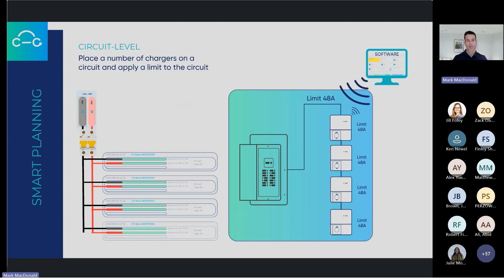If you wanted to get the most functionality, because typically what an electrician would do in that branch circuit scenario, they would put the 4 chargers side by side. 2 people come into that building, let's say I have 20 chargers, they're the only 2 using the charging network, but they're side by side, they're load sharing when theoretically, there's still room on that service for them to have full 48 amp draw on both vehicles. That's where this becomes more common, more money from an infrastructure standpoint, but a better use case for the drivers. This would be a panel level load share.